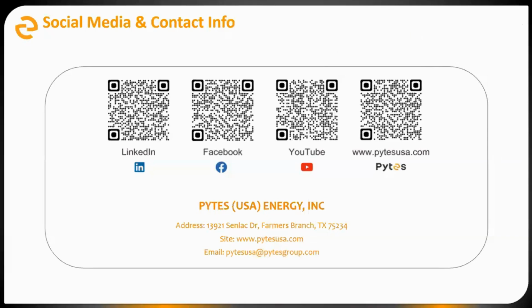Question: can the dry contact be used as an AGS to start the generator at night? Not quite—the dry contact is really more useful for responding to signals, not so much for sending signals out from itself. If you're trying to do automatic generator start, you'll probably be more successful using the inverter to do that. For example, a Sol-Ark has a normally open set of contacts inside of it which you can use for auto gen start.